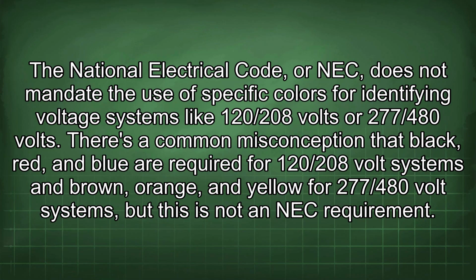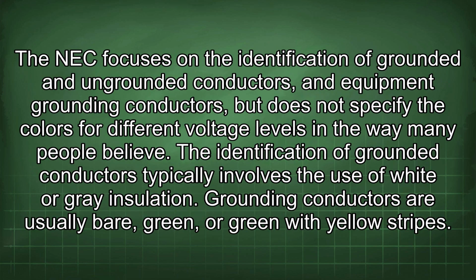The National Electrical Code, or NEC, does not mandate the use of specific colors for identifying voltage systems like 120/208 volts or 277/480 volts. There's a common misconception that black, red, and blue are required for 120/208 volt systems and brown, orange, and yellow for 277/480 volt systems, but this is not an NEC requirement. The NEC focuses on the identification of grounded and ungrounded conductors and equipment grounding conductors, but does not specify the colors for different voltage levels in the way many people believe.